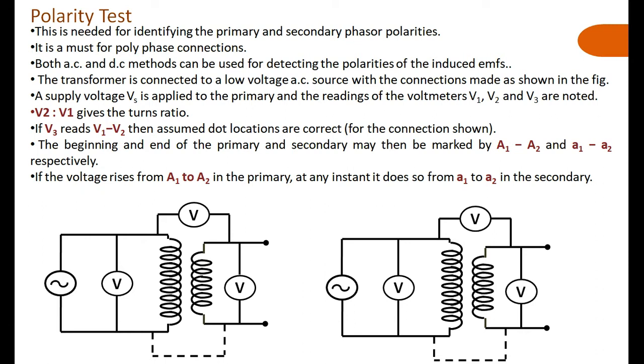The polarity test is necessary to identify the polarity of the primary and secondary windings. At any given instant of time, with respect to the primary and secondary, you have to identify what is meant by polarity. It is a must for polyphase connections — because you have to connect single-phase transformers in three-phase bank connections, it is very essential. At the same time, the polarity test also helps for connecting transformers in parallel as well as for Sumpner's test.